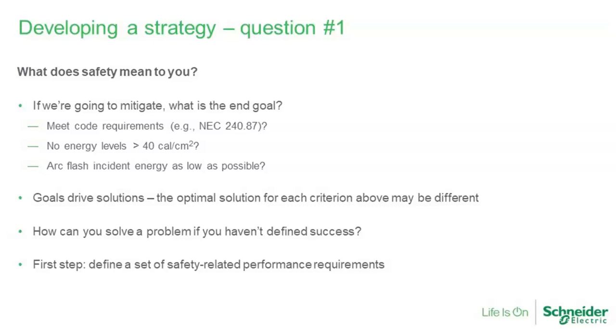If we're going to mitigate, though, I think it's important to really look at what the end goal actually is. Do we just want a system where we meet all the code requirements? We can do that. I showed you the list of things that were called out in NEC 240.87. You can pick whichever one of those seems to be the most appropriate and move on. What if we want a performance level set around incident energy levels? Yes, we want to comply with the code, but we also want to make sure that we meet certain levels of incident energy in our facility. I want no more than 40 calories anywhere in my location. Okay, I can find you a set of solutions that will help you do that.